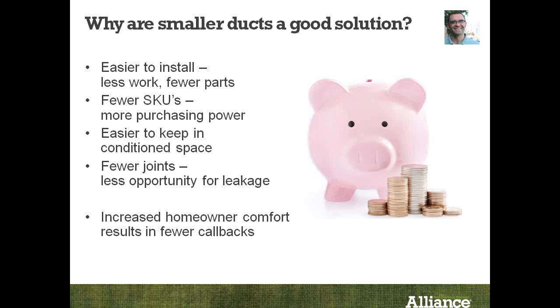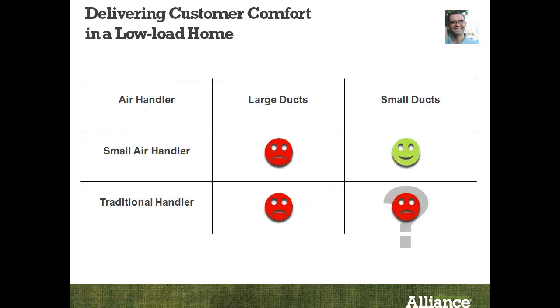Another good opportunity is less leakage. If you have fewer fittings between different types of parts, you're going to have less opportunity for there being a leak. And it's easier to seal consistent parts that are the same size as compared to ducts that keep decreasing in size using your static pressure regain method. What this really means in the end is you can increase your homeowner's comfort, and this results in fewer callbacks. So you're decreasing your risk.